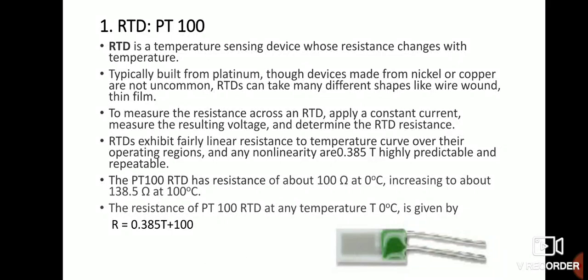Based on Ohm's law, you can easily determine the new resistance value of the RTD. The RTD exhibits a fairly linear resistance-to-temperature curve over its operating range. A common example is the PT100, which is widely used in many applications. The PT100 has a resistance of 100 ohms at 0°C, and at 100°C its resistance is 138.5 ohms.